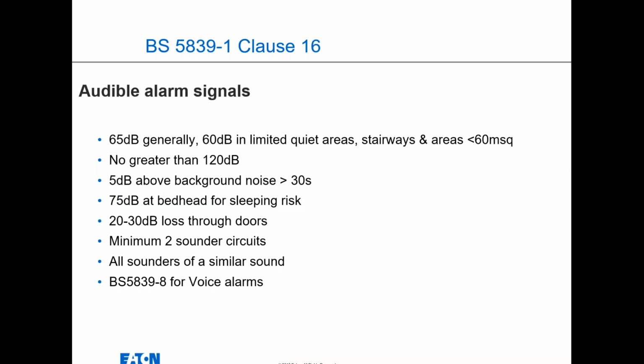So just moving on now to what we spoke about earlier: you've got your smoke detectors and your call points, but you obviously need to make people aware there's a fire. And in the standards, they talk about a common sound level of 65 decibels, and then 60 decibels can be used in quiet areas. Again, if you're working off drawings, how you define a quiet area is tough, so I generally always work on 65 dB.